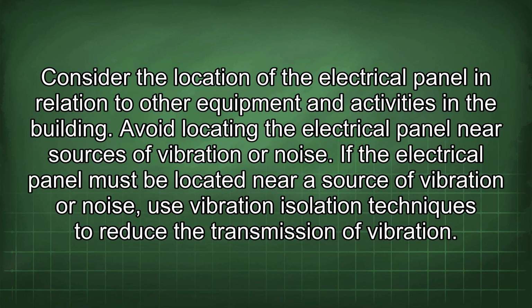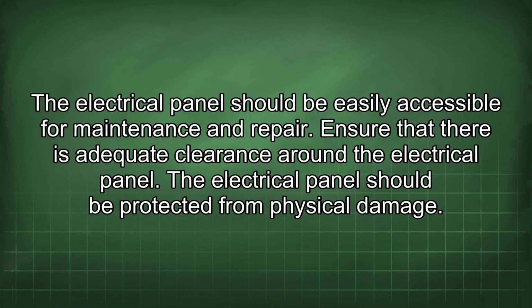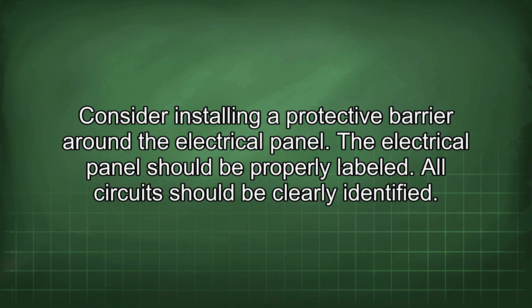Consider the location of the electrical panel in relation to other equipment and activities in the building. Avoid locating the electrical panel near sources of vibration or noise. If the electrical panel must be located near a source of vibration or noise, use vibration isolation techniques to reduce the transmission of vibration. The electrical panel should be easily accessible for maintenance and repair. Ensure that there is adequate clearance around the electrical panel. The electrical panel should be protected from physical damage. Consider installing a protective barrier around the electrical panel.